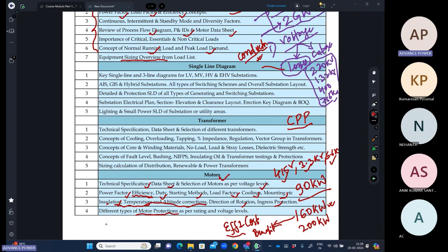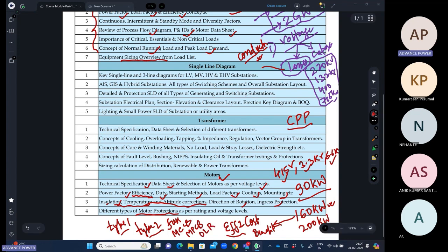Somewhere we might have heard about type 1 and type 2 protection for the motor. Basically, for a motor which is contactor fed and less than 55 kilowatt, we use type 2 coordination. We have phased out type 1 coordination. We'll do the coordination and evaluate the size of the fuse or MCCB or MPCB you are using. We'll calculate the size of the overload relay, the selection of the overload relay, and finally the sizing of the contactor which we are using. So finally it will complete the protection of the motor for less than 55 kilowatt.